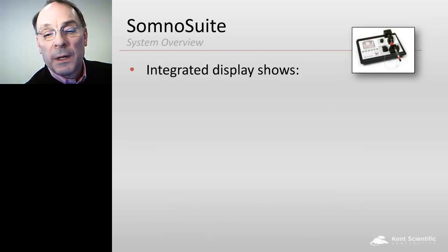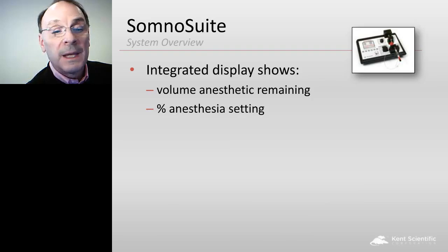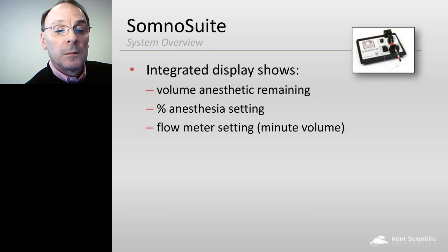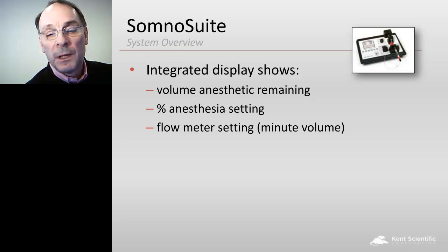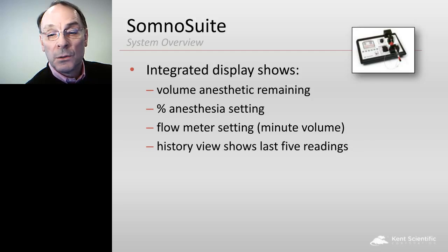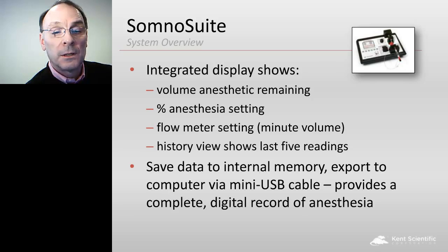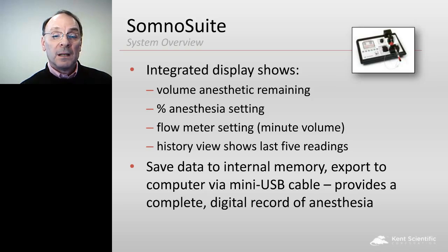The integrated display shows the volume of anesthetic remaining. It shows the anesthetic percent setting. And it shows the flow meter. We call it the minute volume because one of the modules that can be put in here is a ventilator, and in a ventilator we use minute volume as a term for flow rate because it's the amount of air per minute going out or gas going out. So we use this standard term of minute volume. It also shows history, the last 5 readings. You can also save data to an internal memory, and then bring the unit afterwards to a computer and dump the data to a computer.